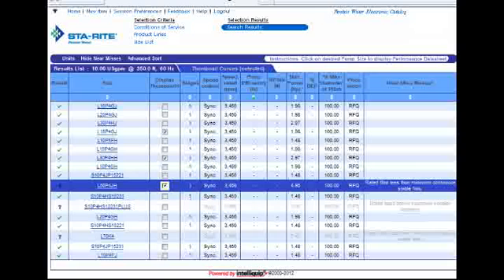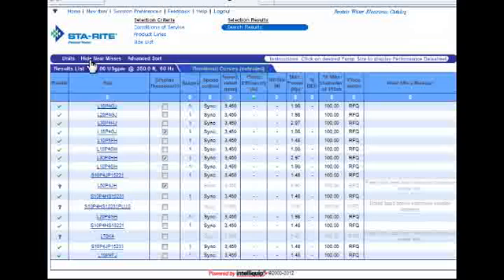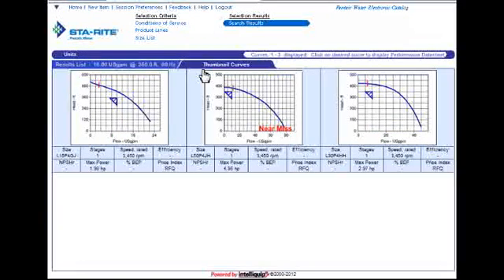Near misses simply mean that some models will work better for some applications than others. You may want to select one of these near miss models anyway because of the cost, or it has other operational qualities that you want from the pump, or any variety of other reasons. With the three models selected that I want to compare, I'll click on the Thumbnail Curves tab at the top of the results list. This gives me a great bird's-eye view of the performance curves of each of these three pumps and where exactly my basic operating data hits on each curve.